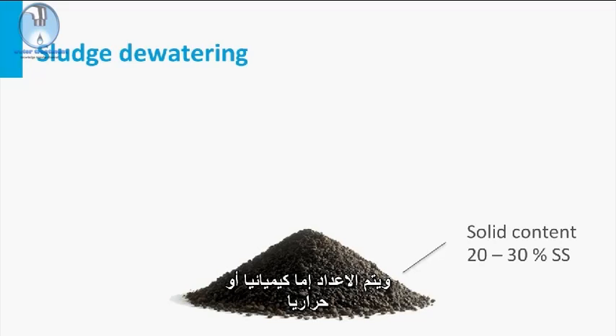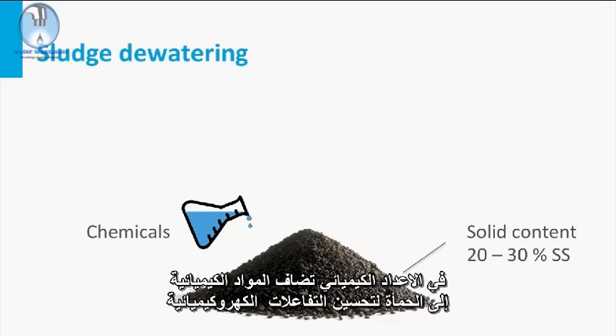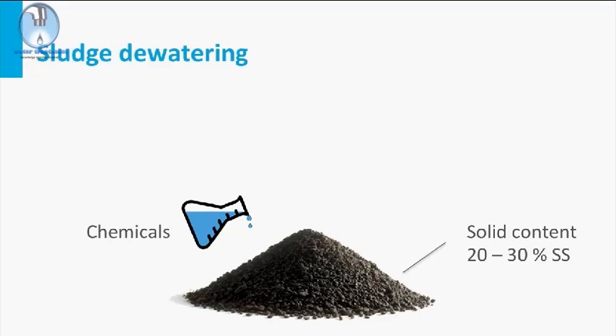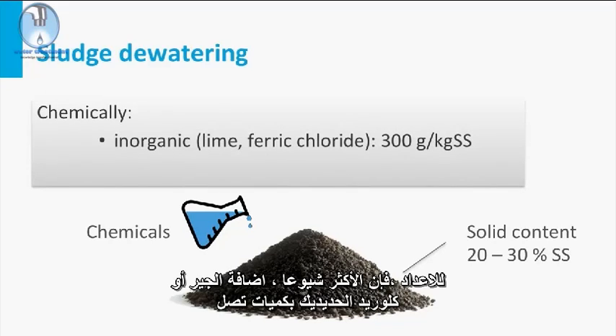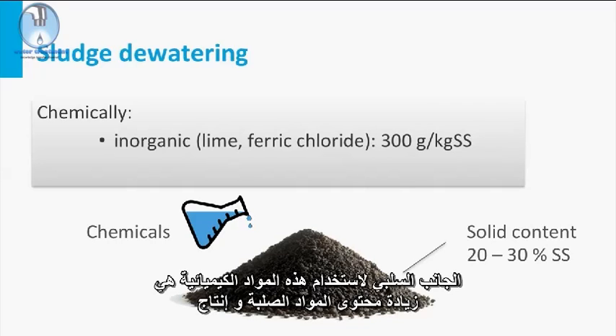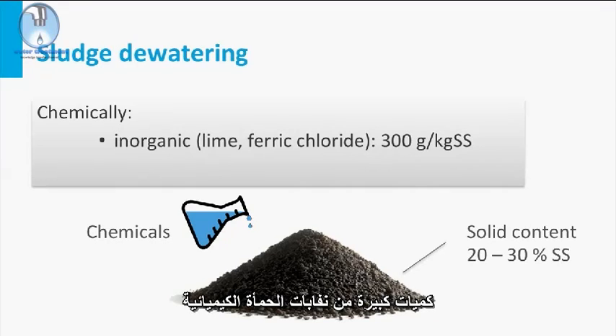Conditioning is done either chemically or thermally. In chemical conditioning, chemicals are added to the sludge to improve the electrochemical interaction between the sludge particles, creating more free water which is easy to separate. Most commonly, lime and ferric chloride is applied in an amount up to 300 grams per kilogram of suspended solids. The downside of using these chemicals is the increase in solids content and the production of large amounts of chemical sludge.